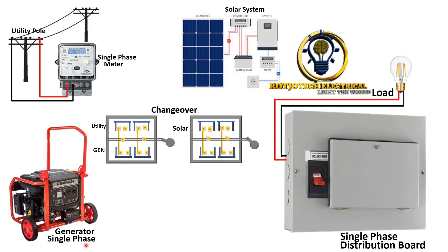What we are going to do first is connect the load side, so that after that we can focus on the utility, solar, and generator connections. We are going to connect both changeover switches together — we loop them together. We loop the live of the first changeover switch with the live of the second, and do the same for neutral. This looped connection serves as our load output.